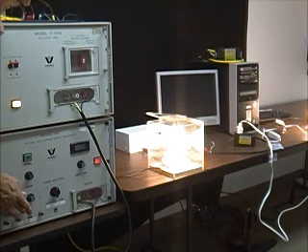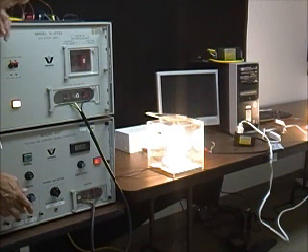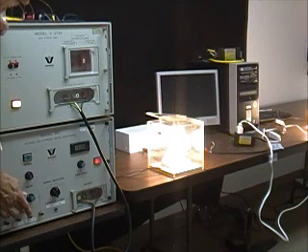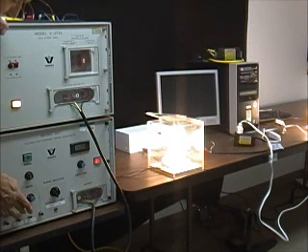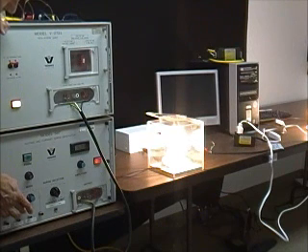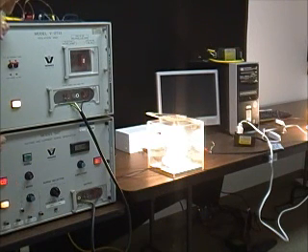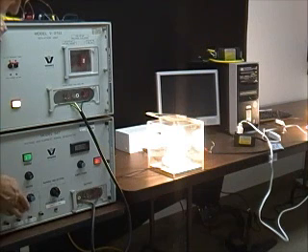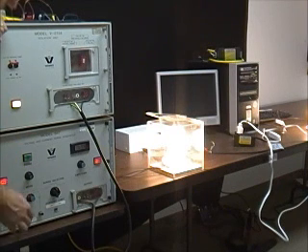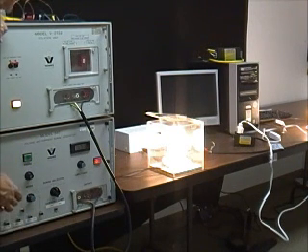One, typically one six thousand volt transient destroys the light bulb. But the positive benefit of the downstream SineTamer suppressor can be seen. Ready to test. Second impulse, first impulse still survived.